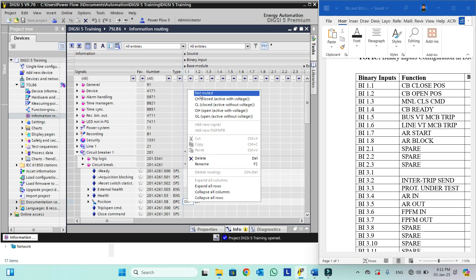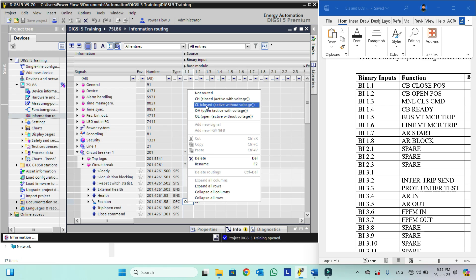The first option is 'not routed'. The second is CH, which means closed active with voltage — whenever this binary input is active with voltage, meaning voltage comes to this binary input, it will be taken as the closed position. The other is CL, which means active without voltage — this is also C meaning closed position.